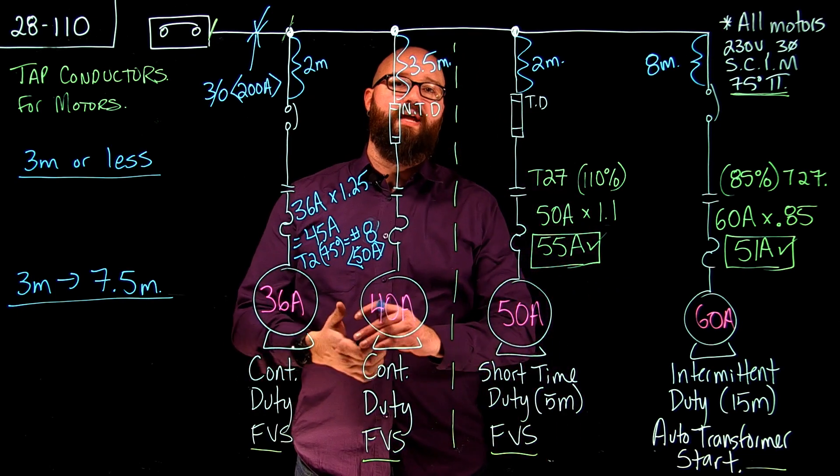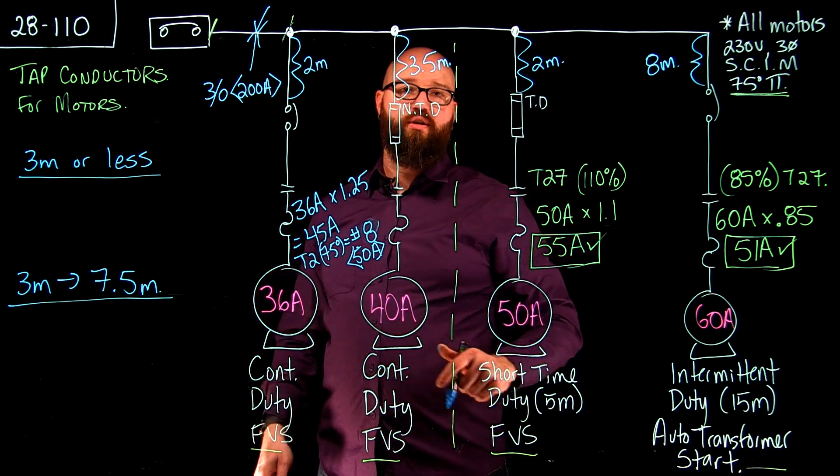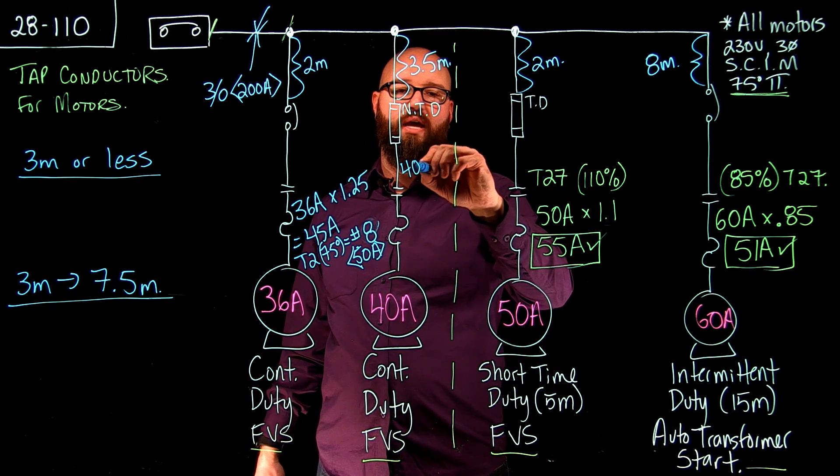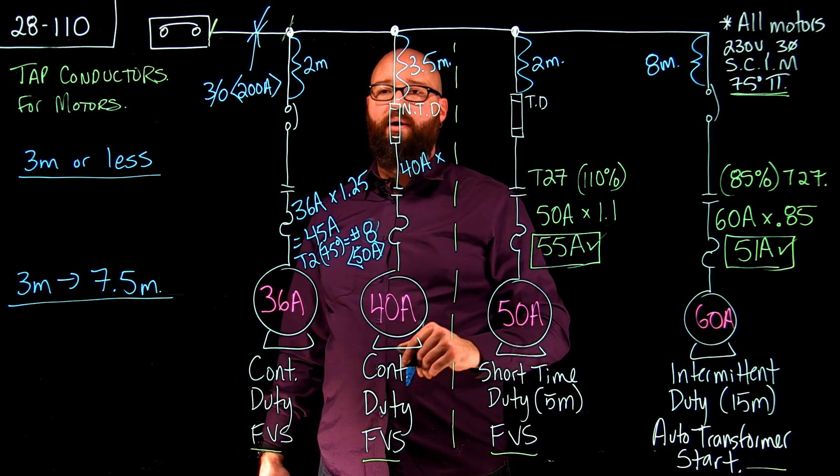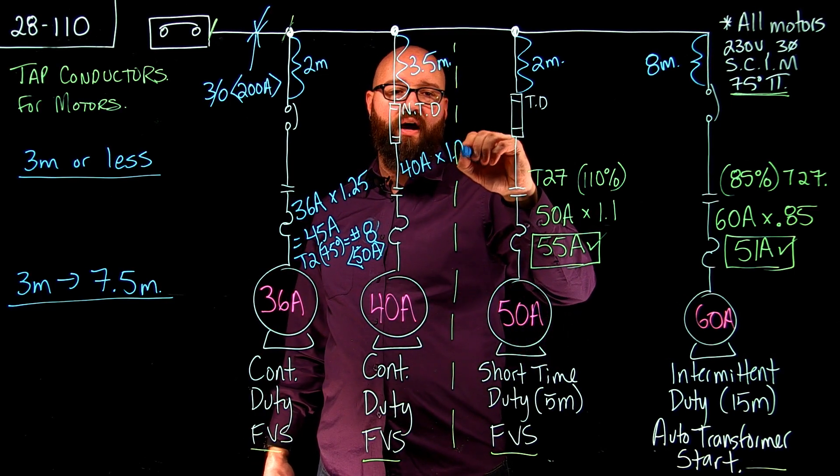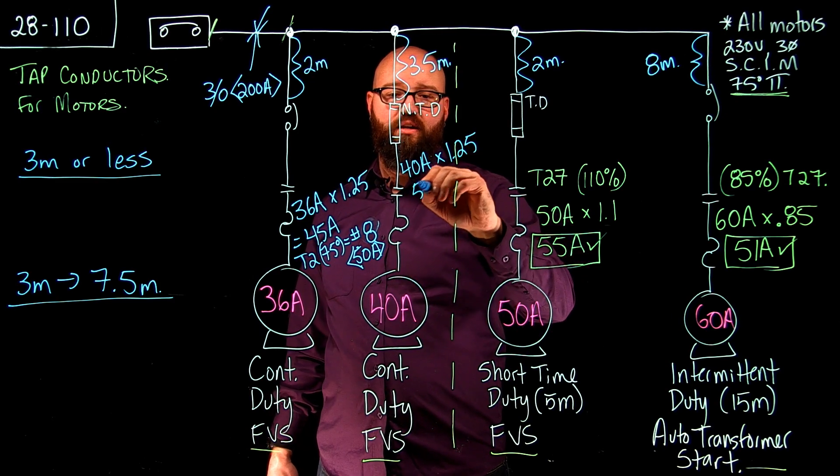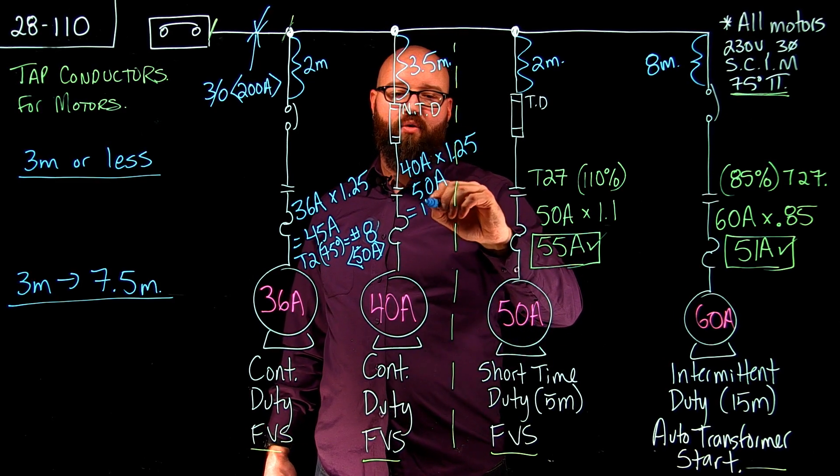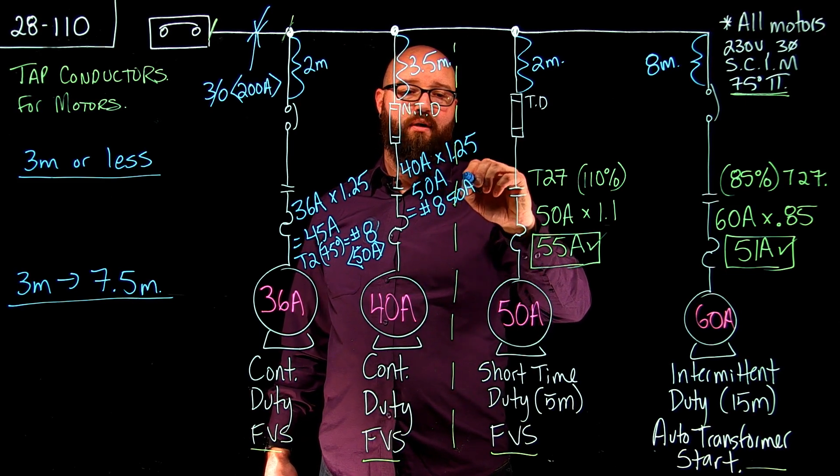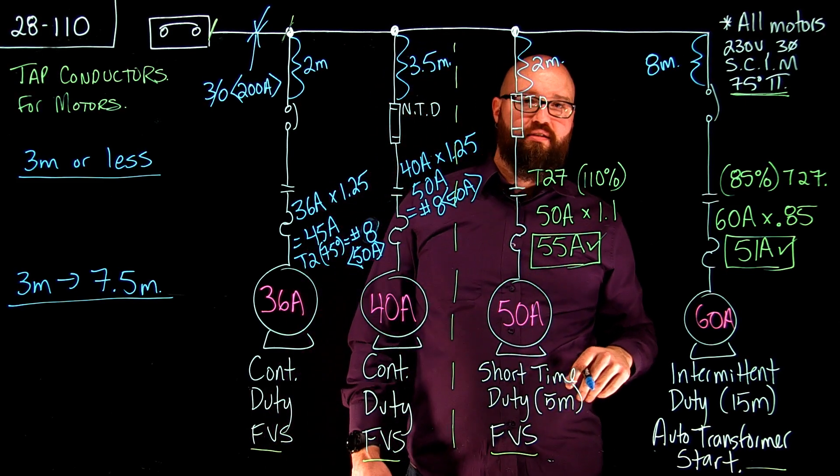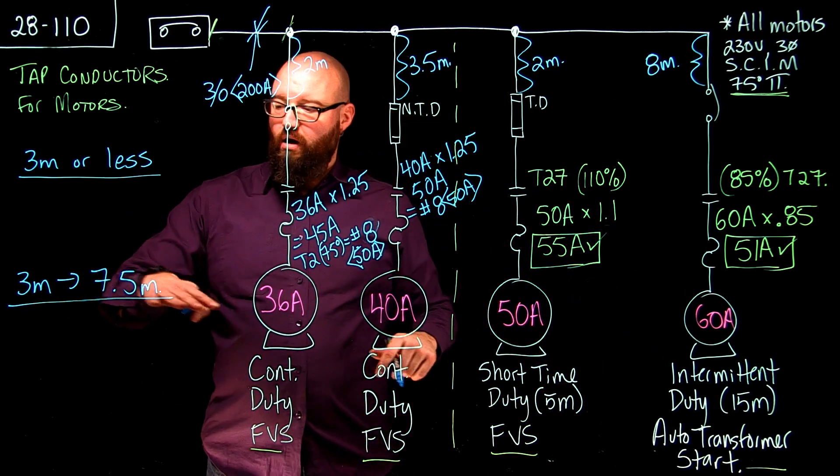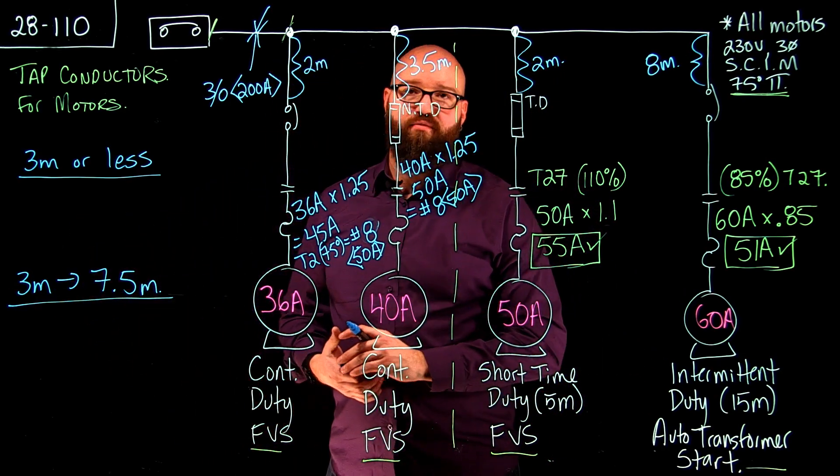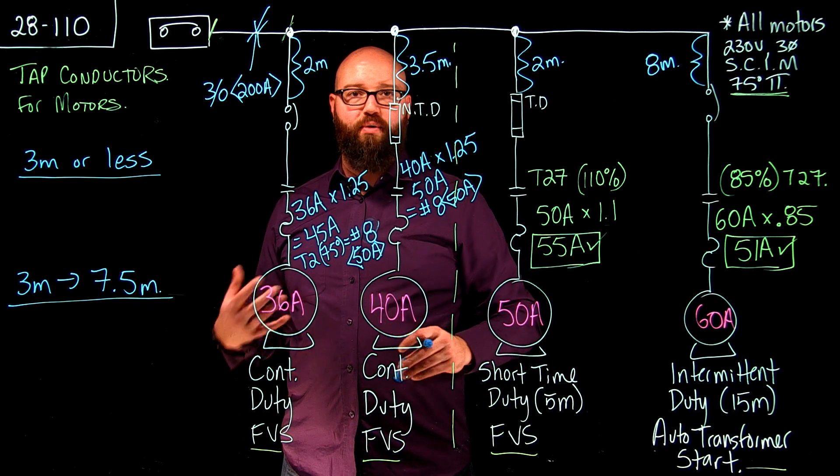On to my 40 amp FLA continuous duty we're going to do the same thing because it's a continuous duty we're going to take 40 amps multiply it by 1.25 which gives us 50 amps. Now again that tells me we would go with a number 8 gauge good for 50 amps but there's one thing we need to keep in mind.